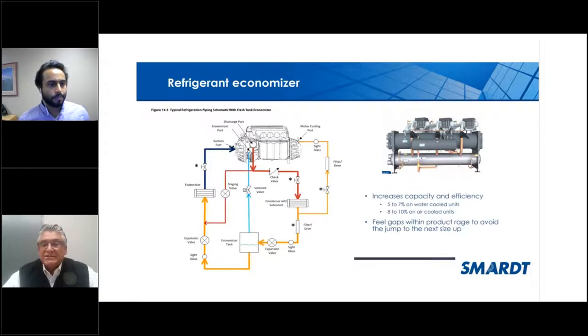So the other addition to this is when you look at multiple stage compressors, there's a couple of different ways you can handle capacity control, and also every chiller, when you look at the capacity, it boils down to dollars per ton, as we all know, right? And it really amounts to the cost of pig iron, if you just be quite frank. The more machine, the more tubes, the more expensive. So anytime you have to jump to a different frame size to get the capacity you need, the price goes up substantially. So with multiple compressors, and ideally a two-stage compressor, you can utilize something called an economizer, which allows the compression to be split between impellers. It increases the lift, increases efficiency, and increases the capacity. It's technology used on a lot of older machines that were low pressure, and multi-stage compressors. So this allows you to do the same thing on a positive pressure machine, medium pressure, positive pressure with multiple stages. So it's a great application, and it has great efficiency and a lot of redundancy.